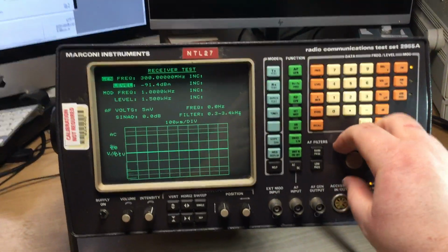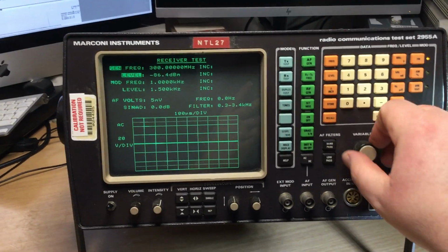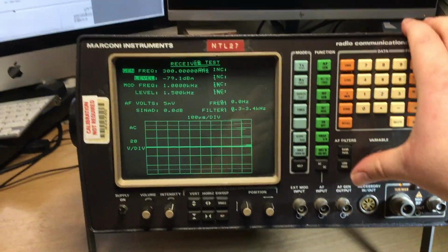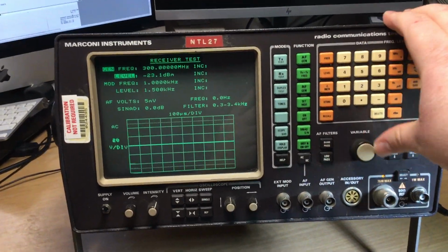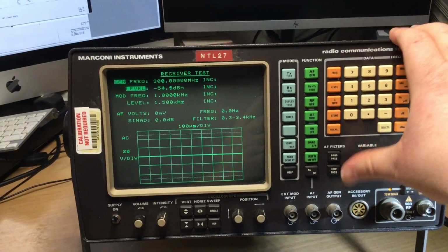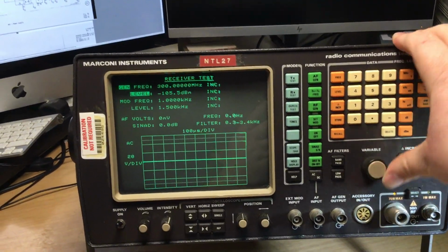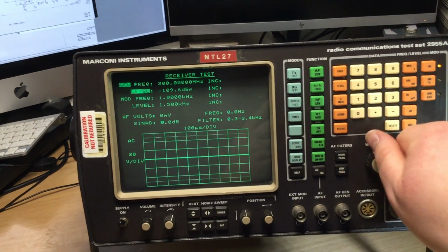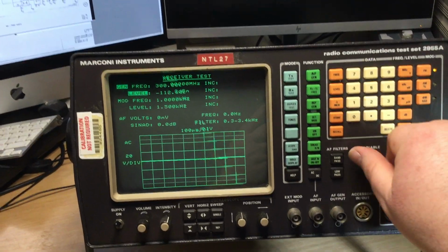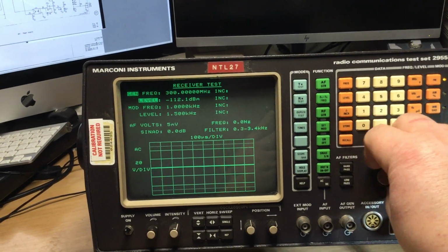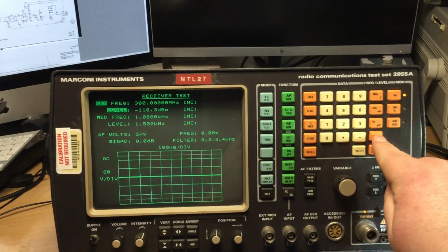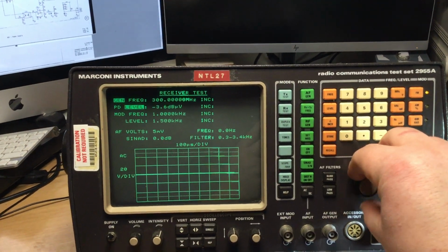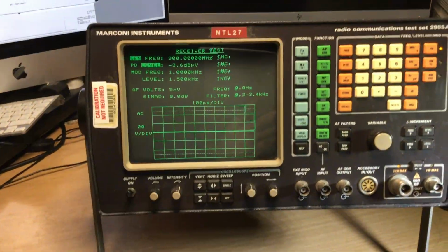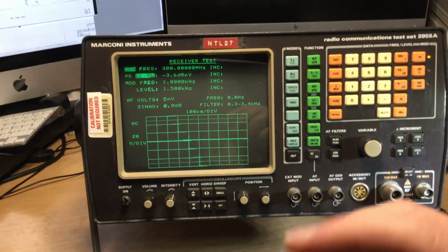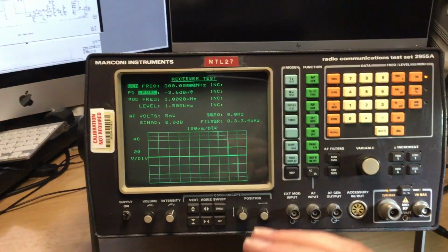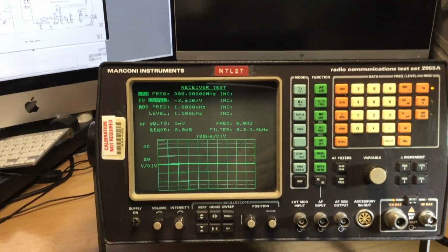So each time you hear a clunk inside, that's turning up to the next step, if you like. So as you can hear in a moment, that's one step there, look, another step, and there are intermediate steps as well in between with a slightly softer click. Now in between those clicks we've got a particular control of level between those clicks, which as you can see on the display there, doesn't matter whether you're reading dBm, microvolts, that needs to be calibrated. So that's the other side to the instrument calibration, is we go into the software mode to calibrate the intermediate steps, and that's done when we look at the RF boards. In a moment I'll explain more closely on how that works.